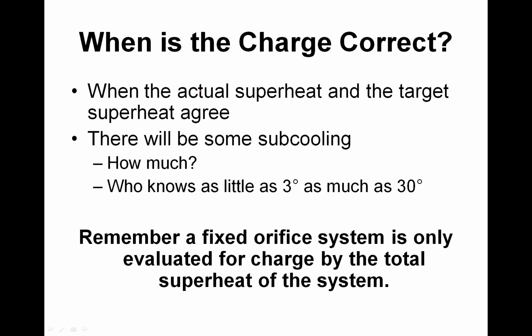Now, we always have to evaluate both sides of the system, because everyone says, well, how much subcooling are we going to have? Well, I have no idea, right? How much is a question. It could be as little as 3 and as much as 30. Because, as we said before, if we had 12 degrees of superheat, we probably have around 10 degrees of subcooling. That's pretty much the way that system's going to be designed to operate, at a single set of conditions. So it's going to operate pretty much like a standard TXV system would under those design conditions. But when we change from design conditions, because its target superheat goes up and down, the subcooling changes also.